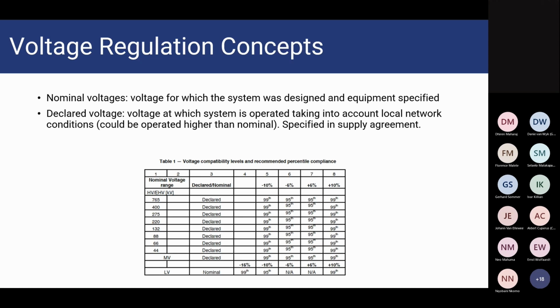Okay, so just a few concepts on voltage regulation before we look into the standard. What is nominal voltage? Nominal voltage is the voltage for which the system was designed and equipment specified. Now, the declared voltage is the voltage at which a system is operated, taking into account the local network conditions. It could be operated at a higher voltage than the nominal.